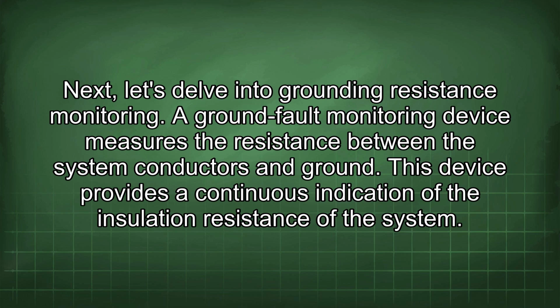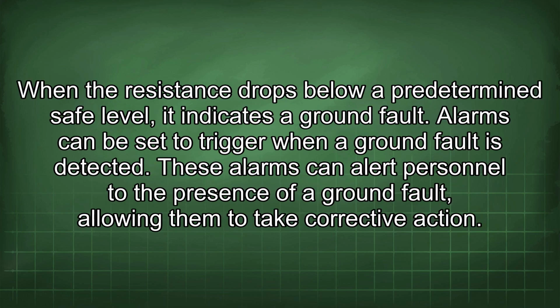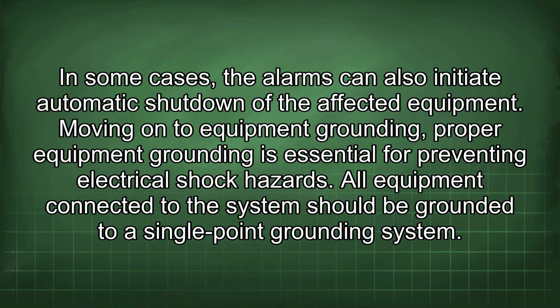A ground fault monitoring device measures the resistance between the system conductors and ground. This device provides a continuous indication of the insulation resistance of the system. When the resistance drops below a predetermined safe level, it indicates a ground fault. Alarms can be set to trigger when a ground fault is detected. These alarms can alert personnel to the presence of a ground fault, allowing them to take corrective action. In some cases, the alarms can also initiate automatic shutdown of the affected equipment.